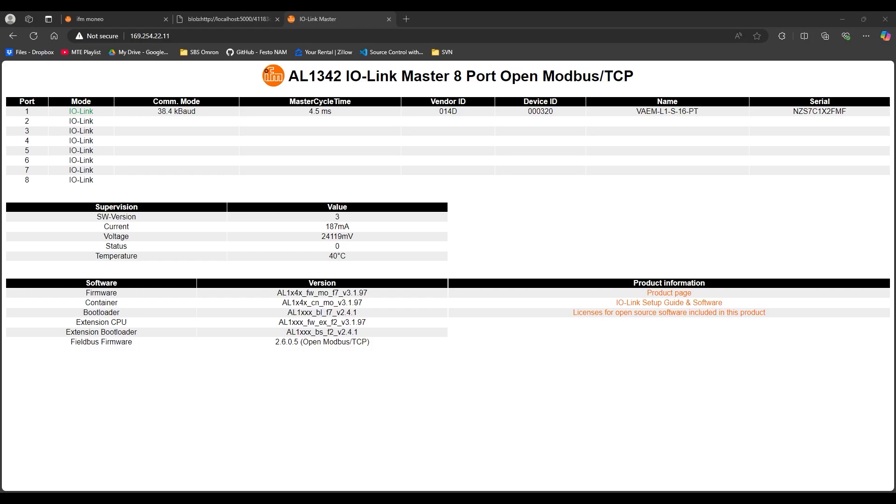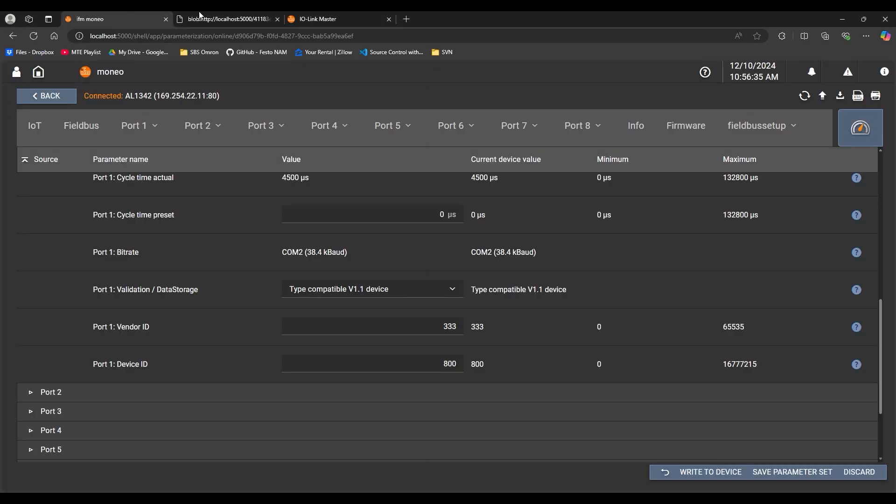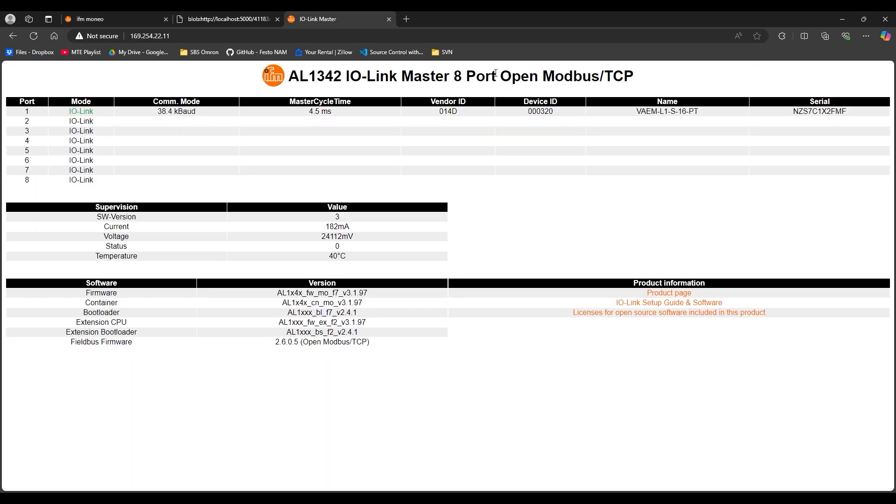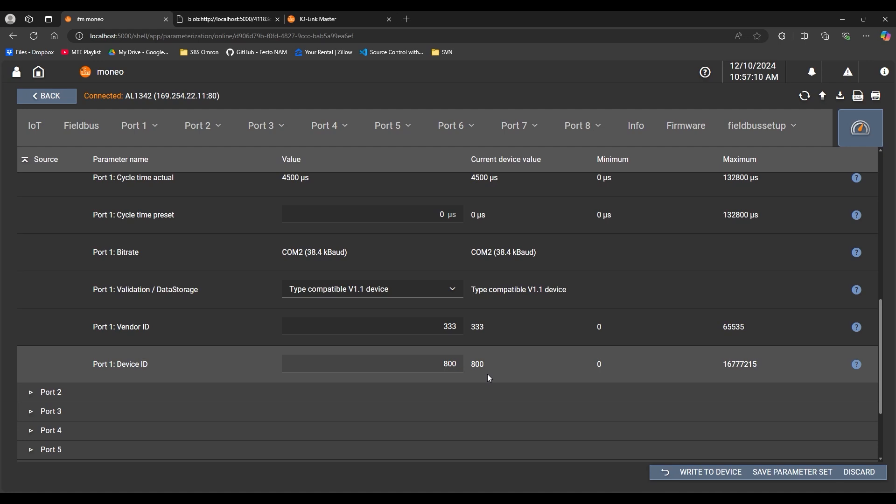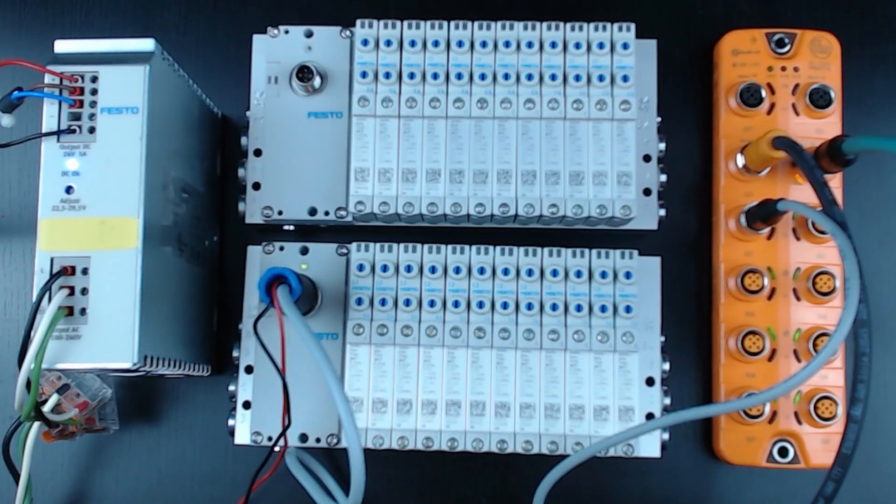Now that we understand the influence of the vendor ID and device ID parameters by port shown here in Moneo, we can use that to our advantage. If I pull a device off of a maintenance shelf or a store that is identical in these two values, vendor ID and device ID, so that's going to be vendor ID 333 for Festo and device ID 800 for this specific variant of the VTUG shown here, the VAEM L1S16PT. If I have these implemented on port one, any other device that I swap in as a maintenance replacement has to match those exact parameters.